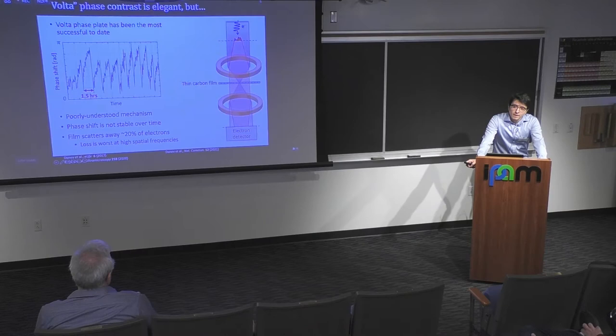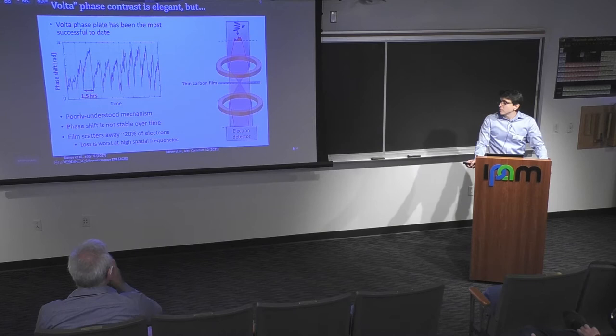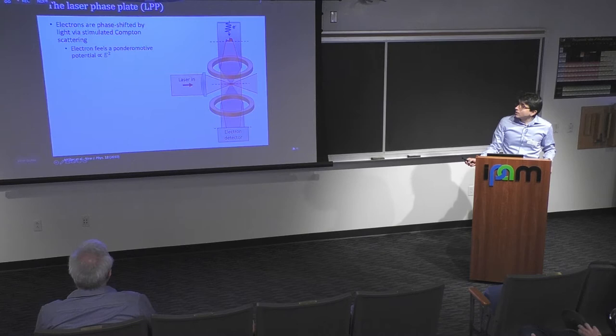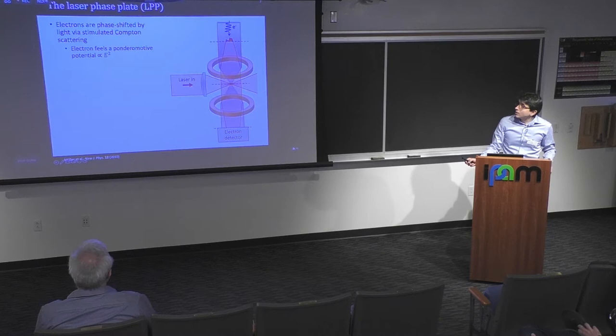The second big problem with the Volta phase plate is that there is quite a bit of scattering of electrons away from the detector — you lose about 20% of your electrons. In cryo-EM we're already dealing with low signal-to-noise, so we really want to keep as many electrons as possible. Our approach in this collaboration between Holger and Bob's groups is to implement a laser phase plate.